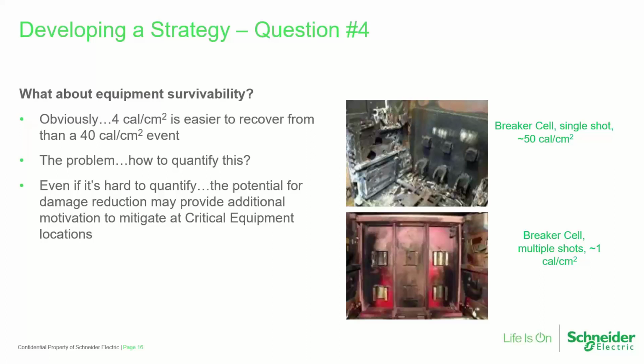It's a tough one to look at. I think this is one where you don't necessarily make this the number one factor in your arc flash mitigation strategy, right? Because nobody wants equipment damage. And if you say, well, I have to have an always on solution, I mean, there's a reason arc flash maintenance switches are popular. They help us deal with some problems that would be hard to deal with otherwise. And so when you're looking at your questions and your criteria, make sure that you don't engineer yourself out of some solutions that would otherwise be very applicable in a real system.